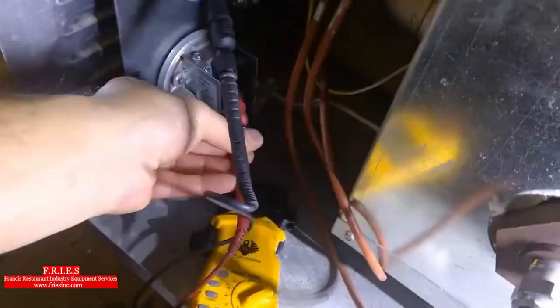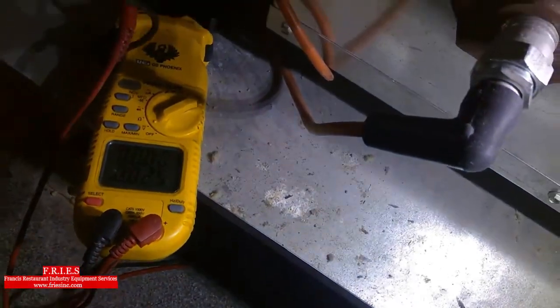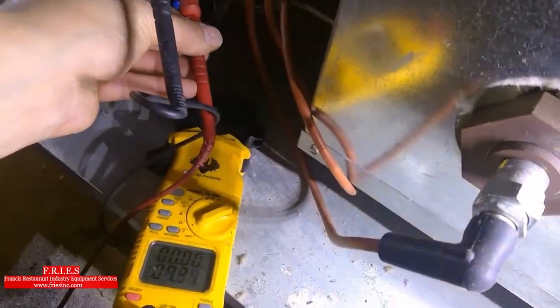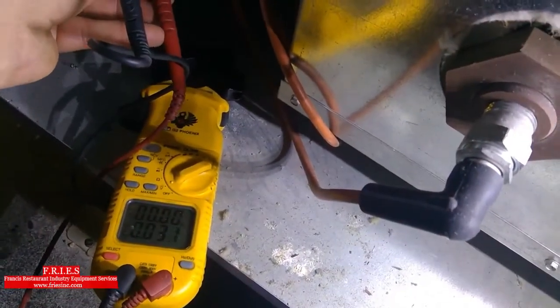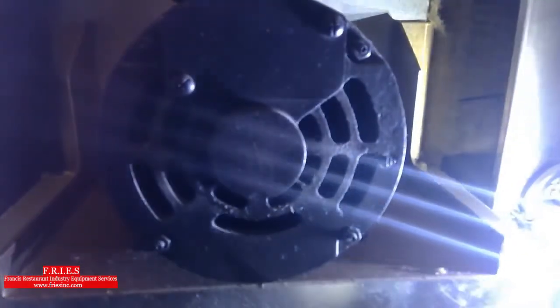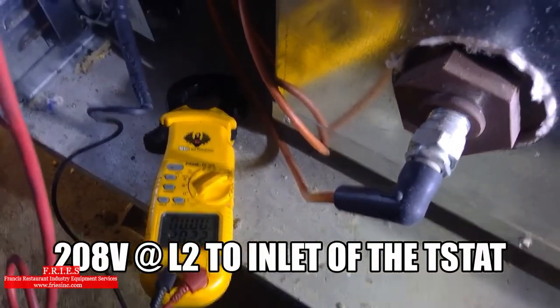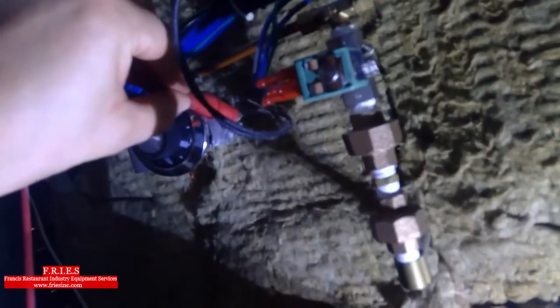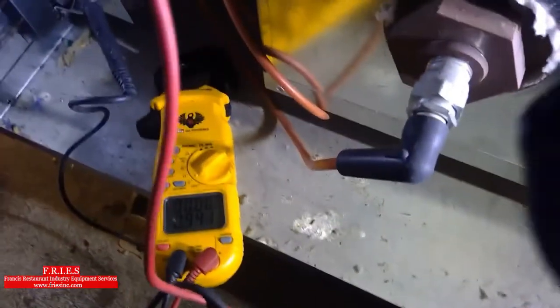Alright, so I'm testing from L2 to the outlet of the pressure switch, 0 volts. L2 to inlet of the pressure switch, 0 volts. Next I'm going L2 to the inlet of my thermostat. I'm getting 208 from L2 to the inlet of the thermostat. Next, I'm going to test L2 to the outlet of the thermostat. I'm getting 0 volts there.